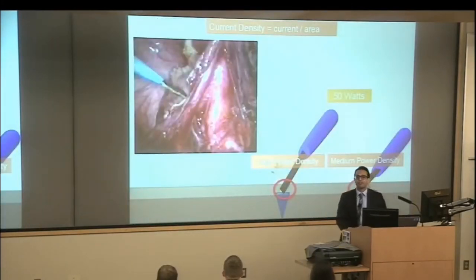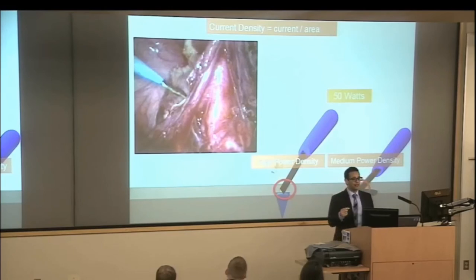Another very important principle is current density. The amount of thermal effect you get when you apply current is directly proportional to the square of current density. Current density is the amount of current that goes through your circuit divided by the surface area through which that current is traveling. The more dense that current is, the more thermal effect you get, whereas if it's less dense or spread over a broad surface area, like the dispersive electrode, the lower the thermal effect.